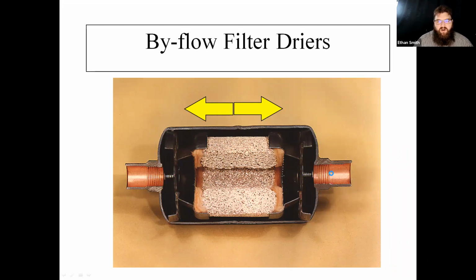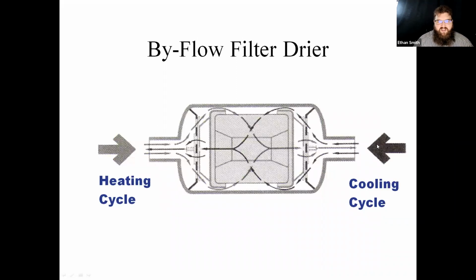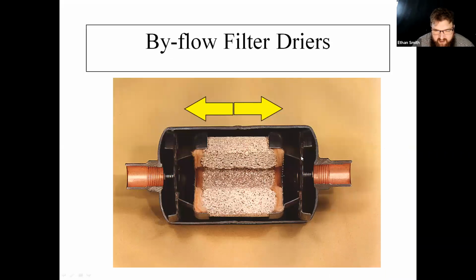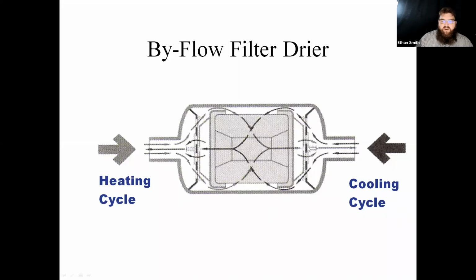So the way these things work is, depending on which side you're coming in, it's always going to go up through this. It's actually got two check valves in here. It's got a little leaf valve, which you can just barely see right here. It's a little spring valve right here. And it's going to allow refrigerant to come up, pass through that passage, go through the outside of the core to the interior of the core, and then open this spring-loaded check valve here and flow out the other side. So just like is pictured there, we've got our little check valves here, and we've got some spring checks on this plate here as well. And so we're always filtering from the outside in.